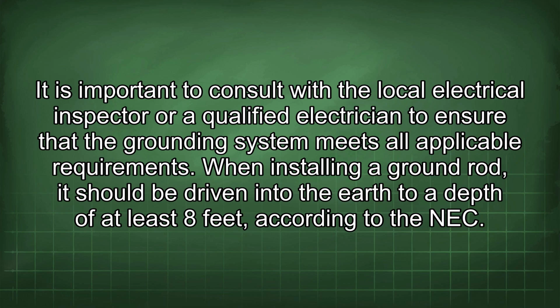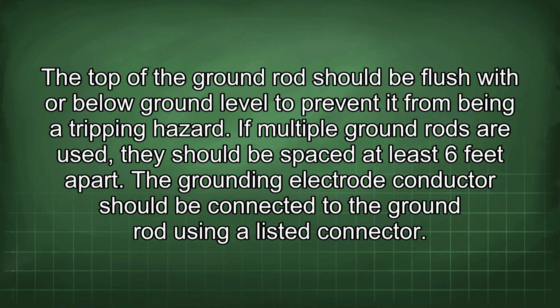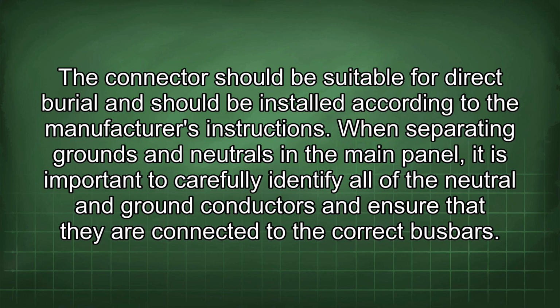When installing a ground rod, it should be driven into the earth to a depth of at least 8 feet according to the NEC. The top of the ground rod should be flush with or below ground level to prevent it from being a tripping hazard. If multiple ground rods are used, they should be spaced at least 6 feet apart. The grounding electrode conductor should be connected to the ground rod using a listed connector. The connector should be suitable for direct burial and should be installed according to the manufacturer's instructions.